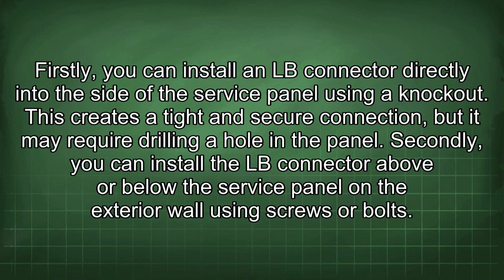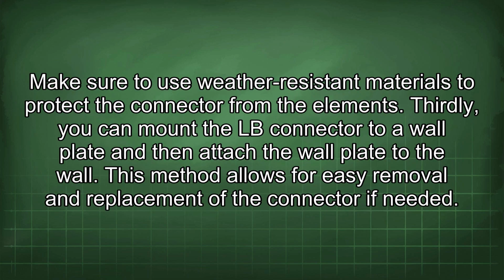Firstly, you can install an LB connector directly into the side of the service panel using a knockout. This creates a tight and secure connection, but it may require drilling a hole in the panel. Secondly, you can install the LB connector above or below the service panel on the exterior wall using screws or bolts. Make sure to use weather-resistant materials to protect the connector from the elements.